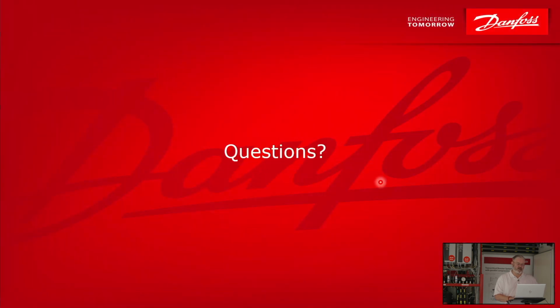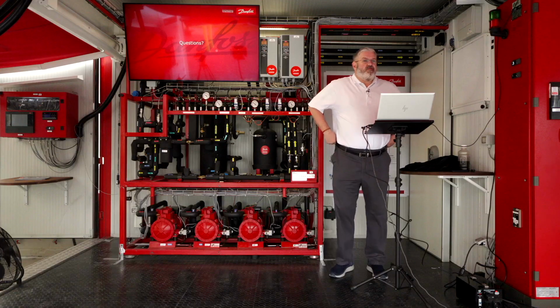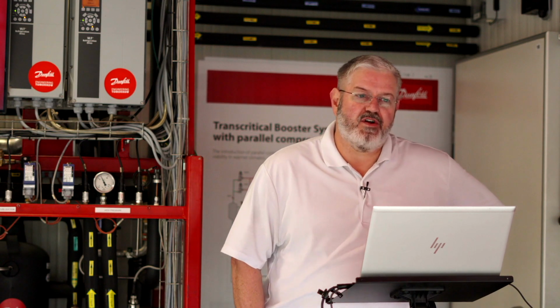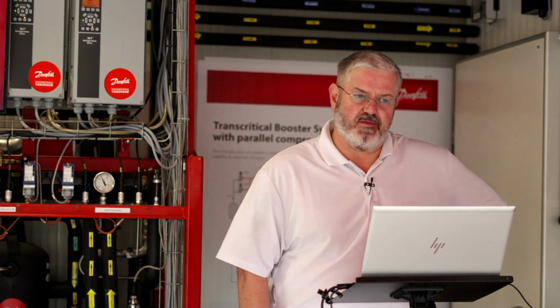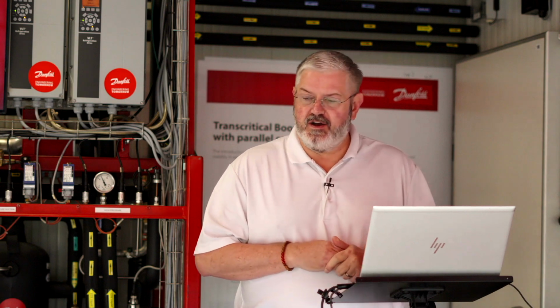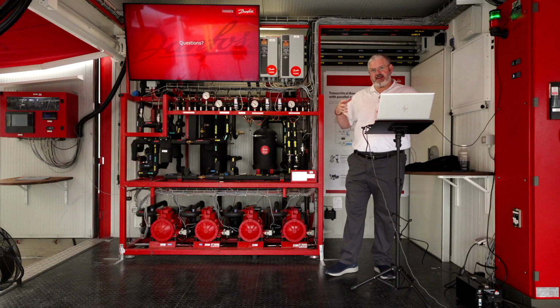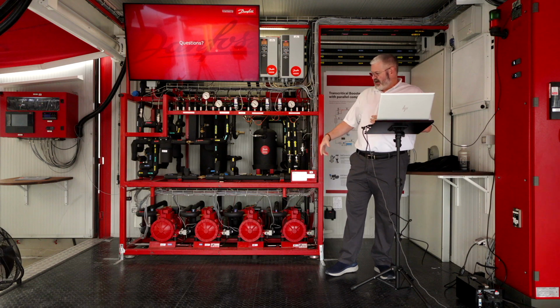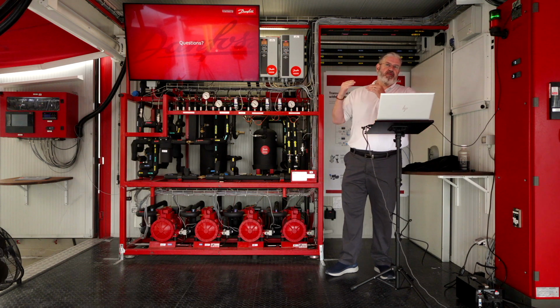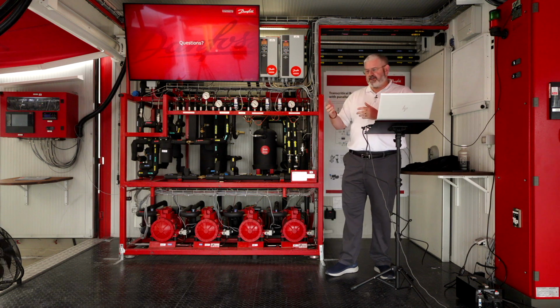And here we are for questions. Do we have any questions? So we have a question that's asking, do you need a parallel compressor for each compressor on the rack? The answer to that would be no. We have two here because it works out nice and tidy. We've got two evaporators, so we size a compressor for each evaporator, and then parallel compression. We were a little above what one compressor could handle, so we added a second one.